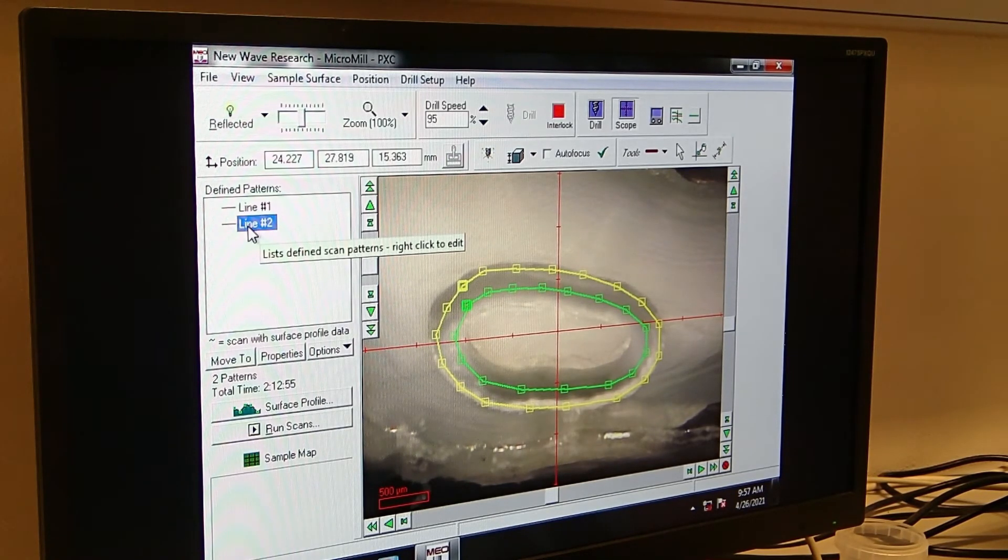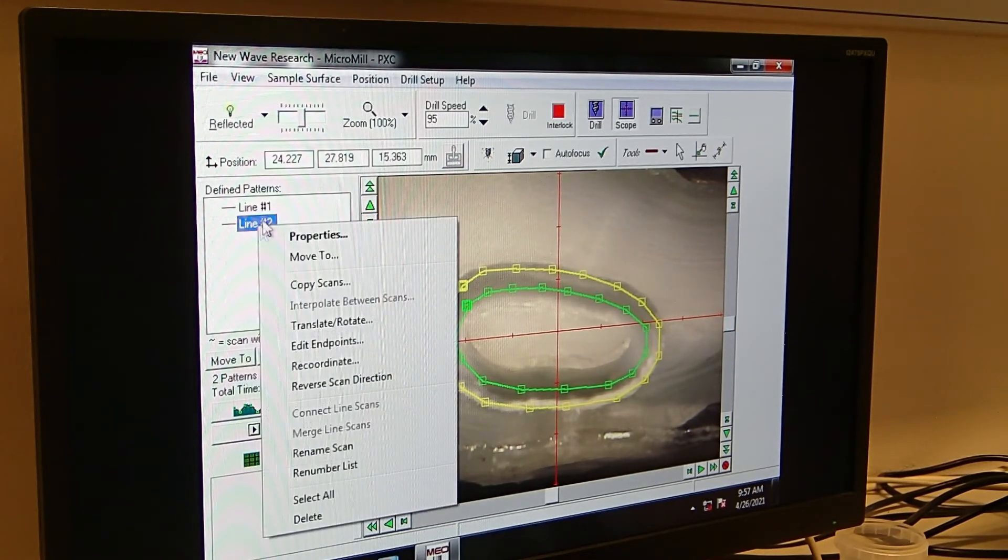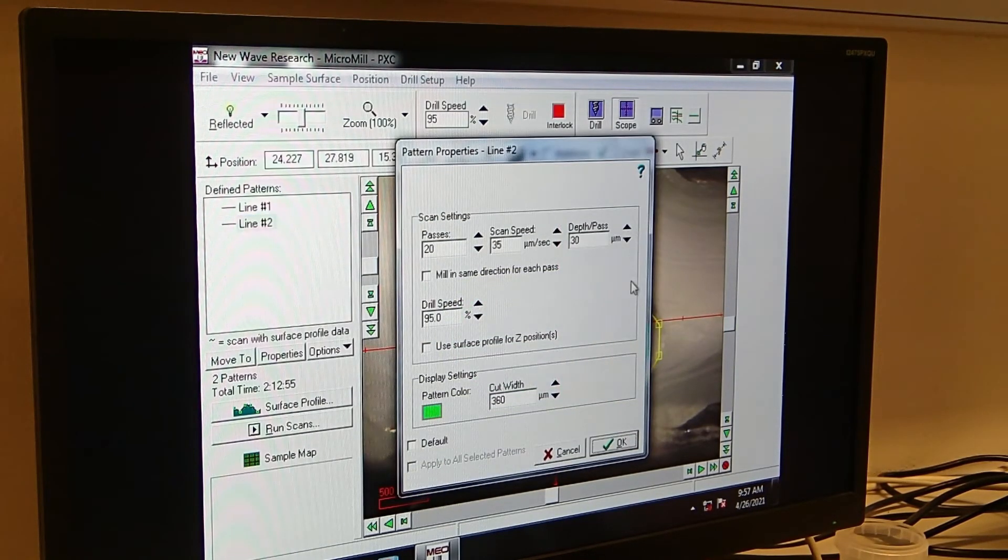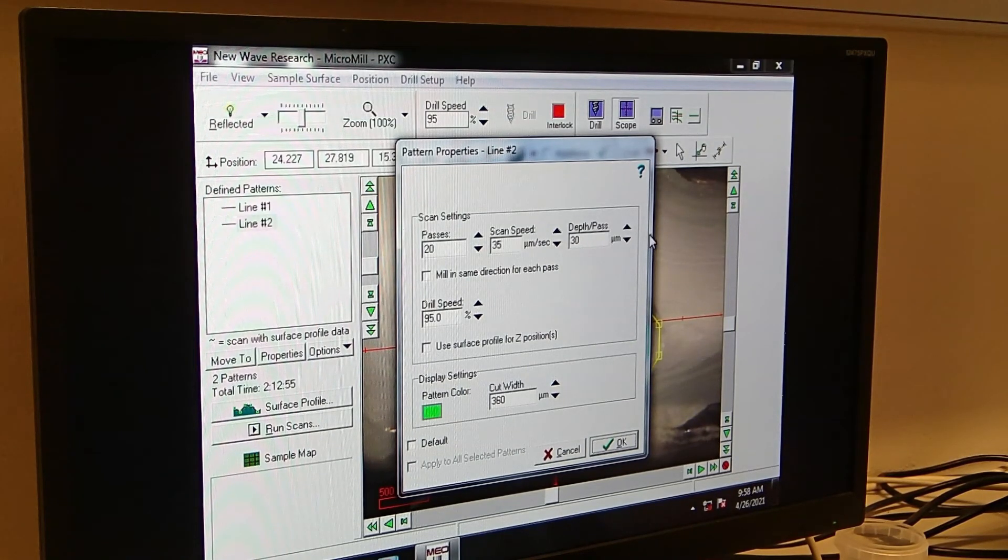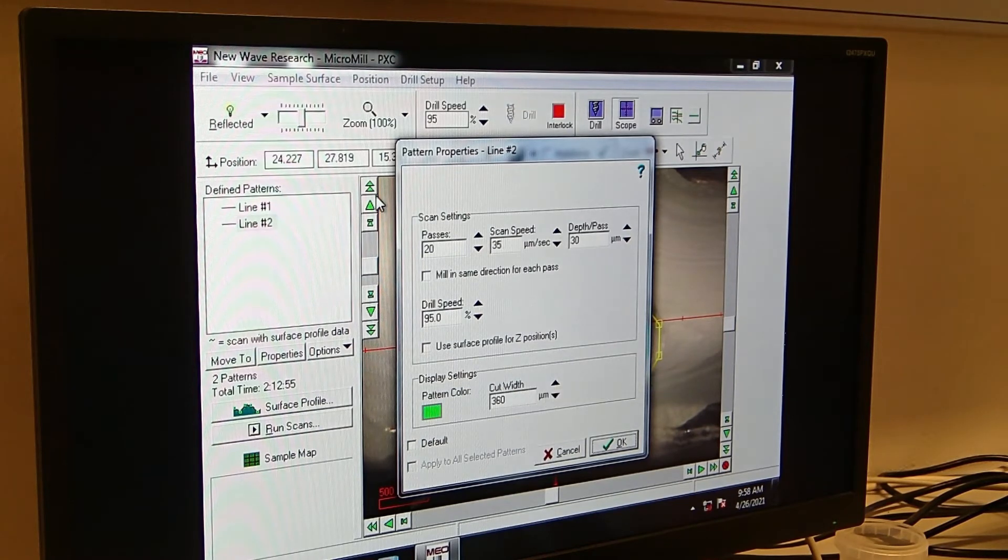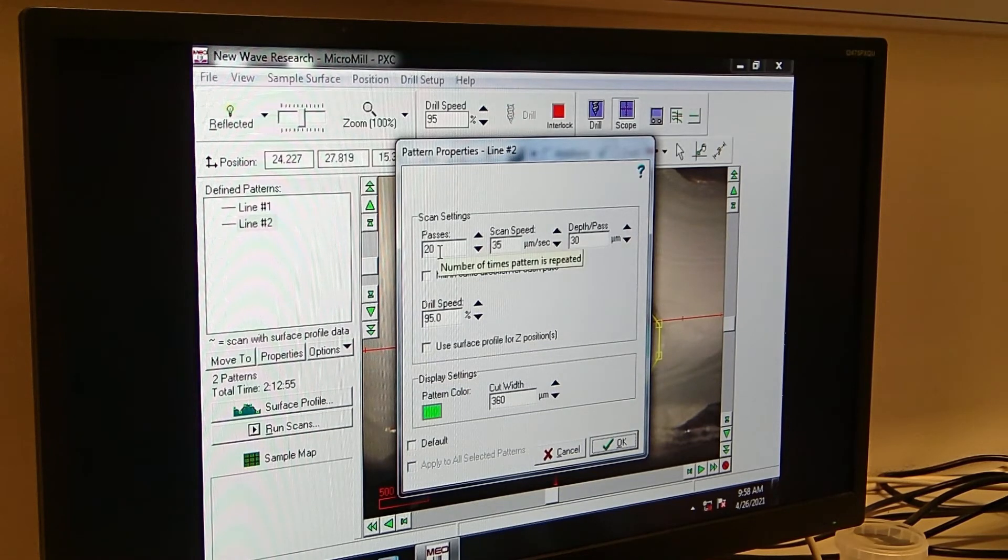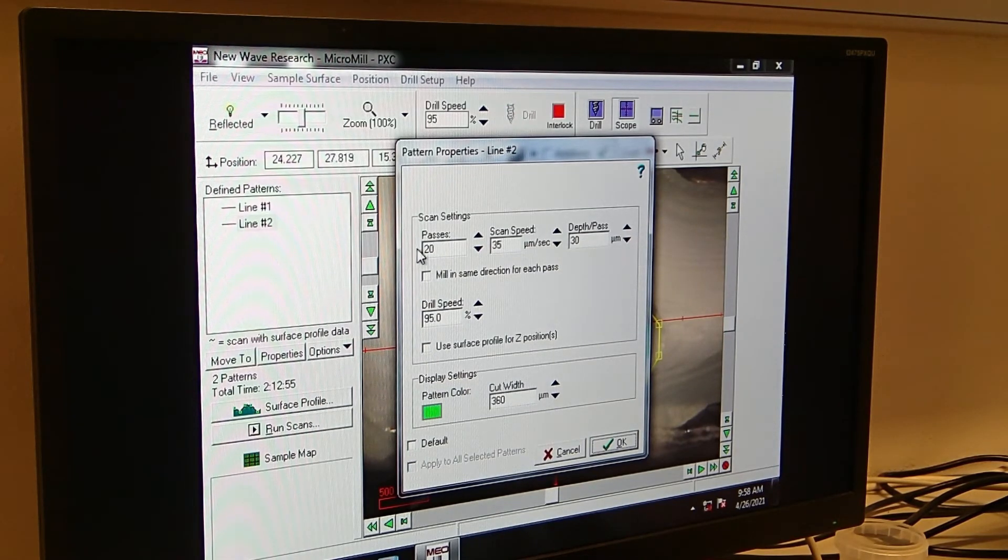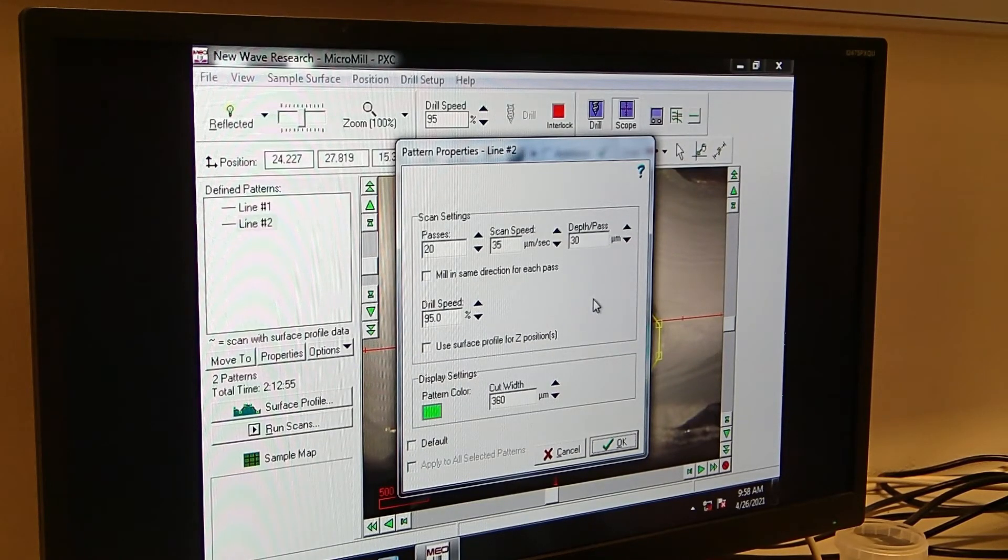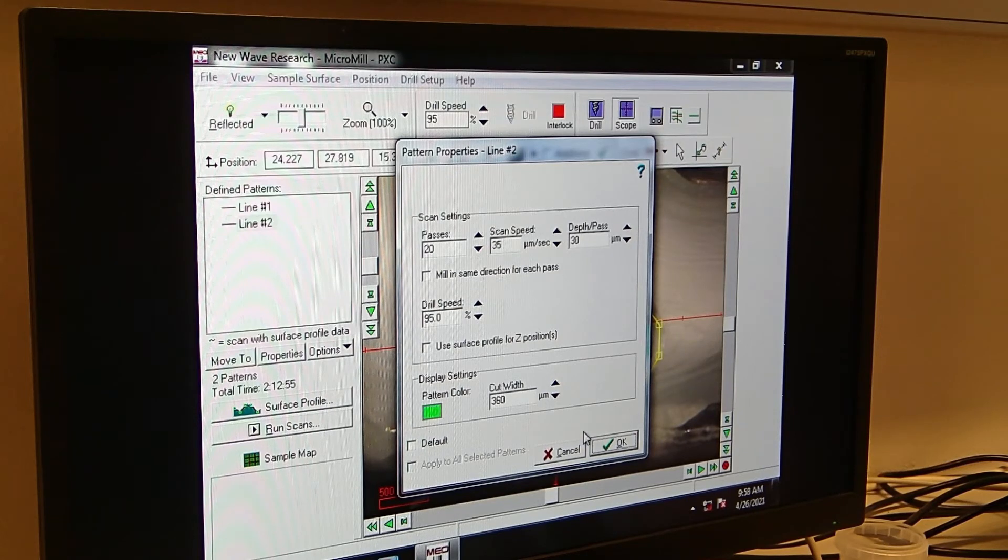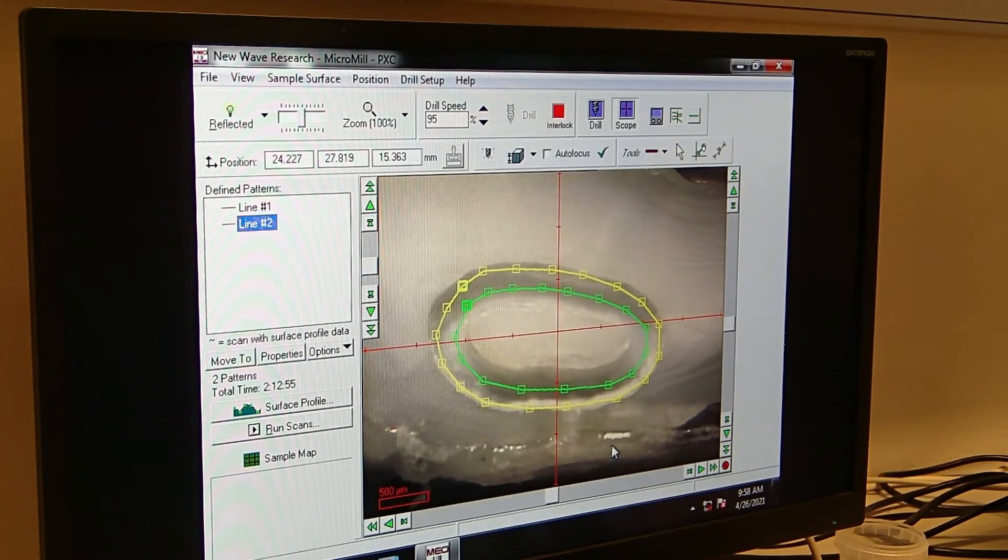So now actually to the setups of the drill pattern and the defined pattern we're interested in. So as I said, we click on the line, then it's with the left, then it's right click and we do go to properties. So these passes are the ones which are the default ones and usually work very well for cod otoliths. So this is the number of passes, the scan speed and the depth per pass. And then you can calculate how deep you go. So 30 times 20 is 600, so you're going to drill about 600 micrometer deep. So this is all perfectly set up. You don't have to make any changes here and you can click on OK.